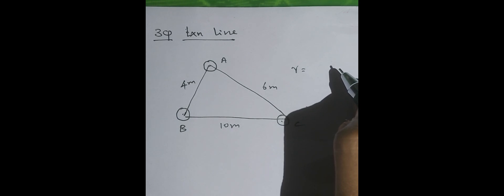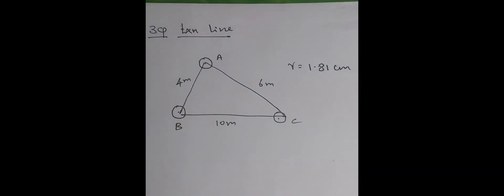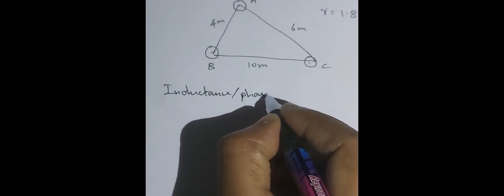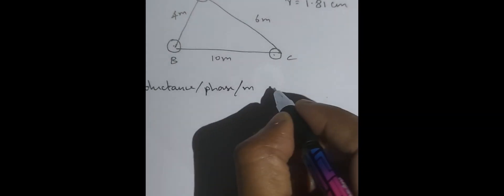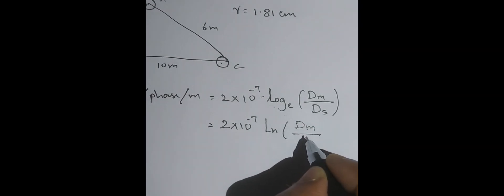If diameter is given instead, you have to find out the radius. Radius is 1.81 centimeter as per the problem. Now we know inductance per phase per meter is: 2 × 10⁻⁷ × ln(dm / ds), where dm is the mutual GMD and ds is the self GMD, which is nothing but the geometrical mean radius.